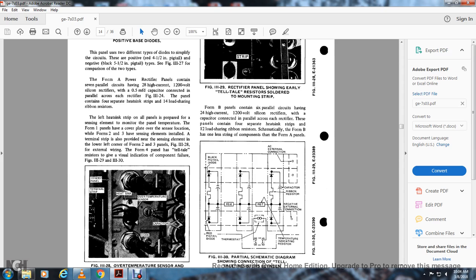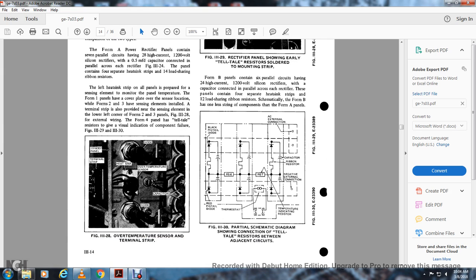Form B panels contain 6 parallel circuits having 24 high current, 1200 volt silicon rectifiers, with the capacitor connected in parallel across each rectifier. These panels contain 4 separate heat sinking strips with 12 load sharing ribbon resistors. Schematically, form B has one less string of the components of the form A panels. Figure 330: partial schematic diagram showing connection with the telltale resistor between adjacent circuits.